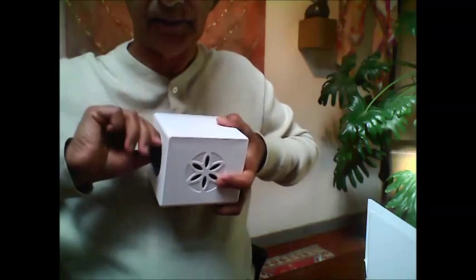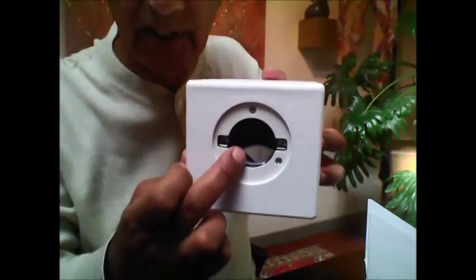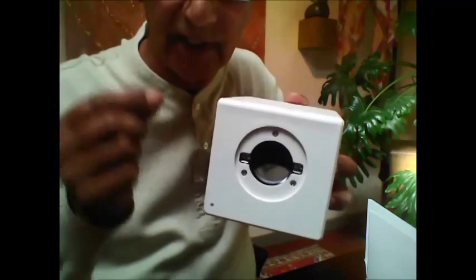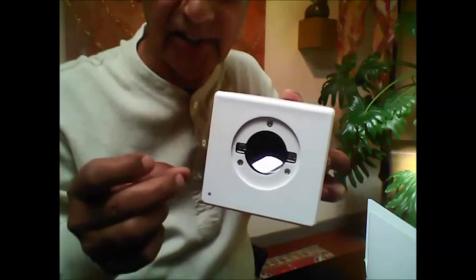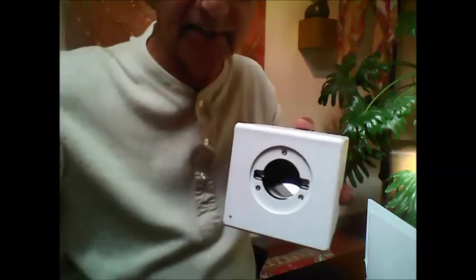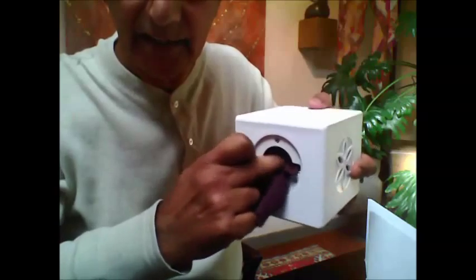Place the thumb in here, place the forefinger, and pull it straight out. Having done that, now you see on the inside — this is the glass electrode that you are looking at. This is where all the information is gathered. So we must be very careful that we do not damage it. That surface is always to be kept very clean, preferably with a non-alcoholic lens cleaner — a high quality camera lens cleaner. You can use a soft chamois cloth and gently clean the surface.